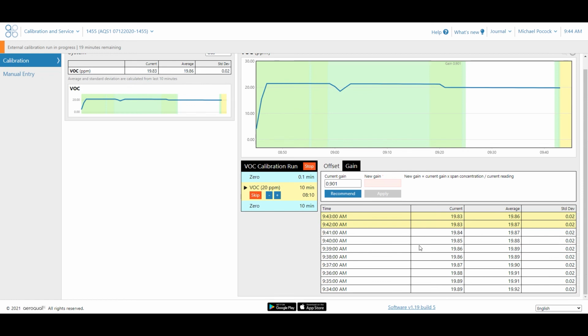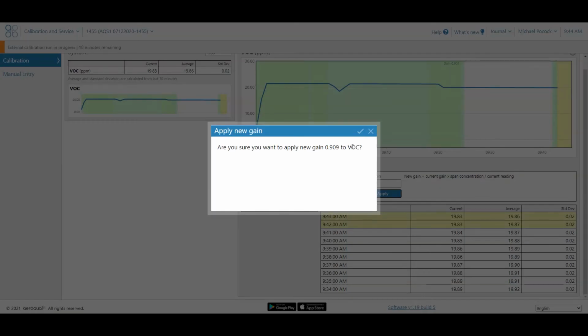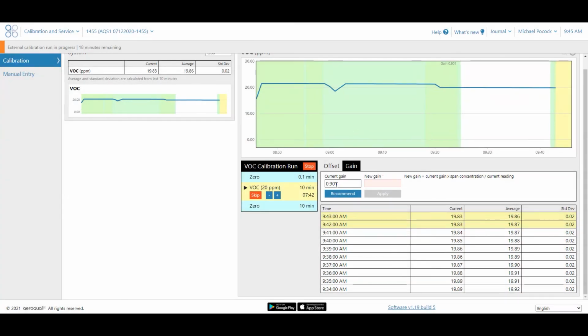If this number was outside of the range 19 to 21, then we would want to change the gain. To do that, we would hit recommend, and then we would hit apply. What that would do is tell the monitor that it should be reading 20 ppm instead of whatever it's reading. I can click apply there, and it will say, do you really want to apply this gain? Yes, I do. And that is probably just going to bring that number up to exactly 20.